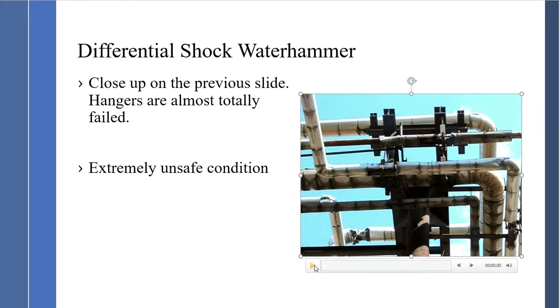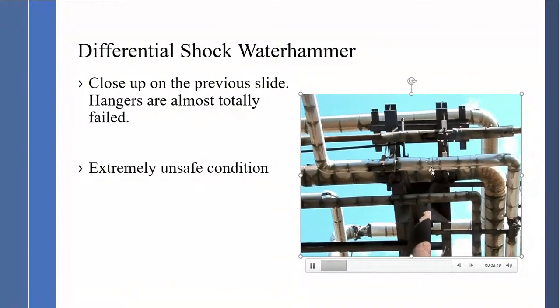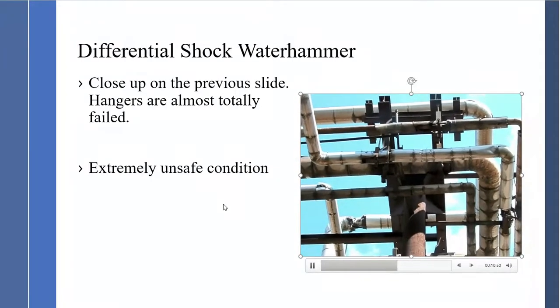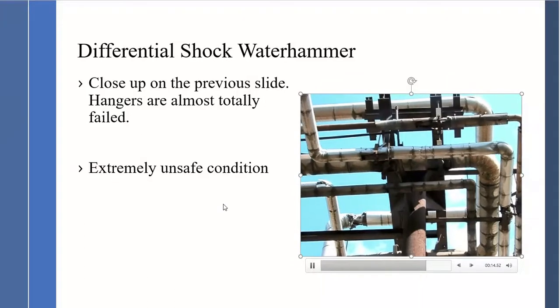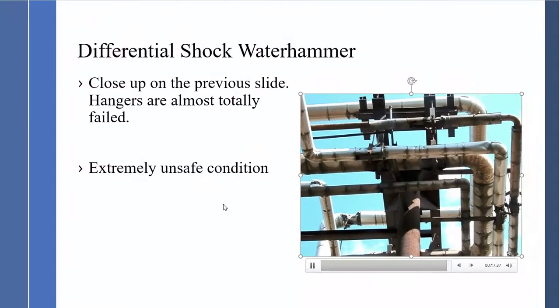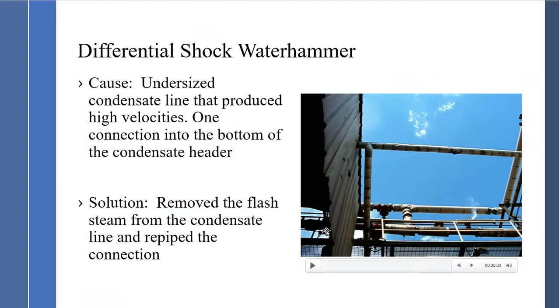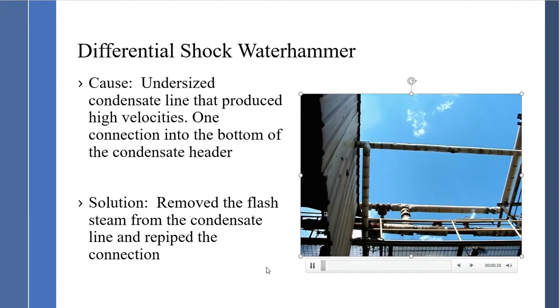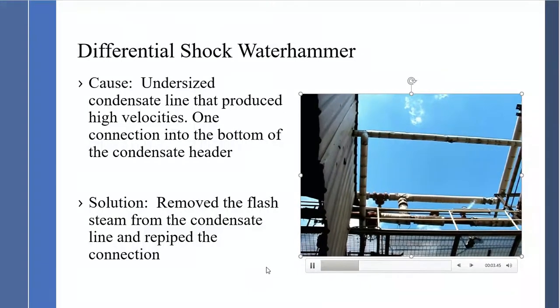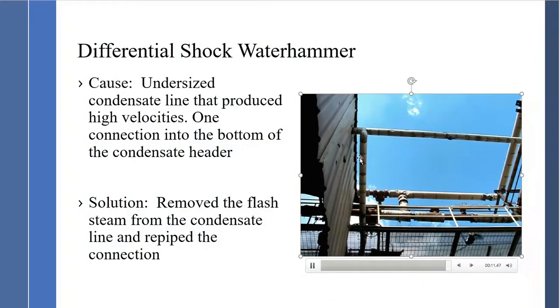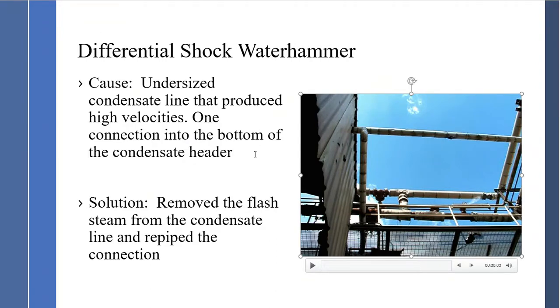A close-up shows visible damage to the pipe support from the water hammer effect. This was an unsafe condition due to plant personnel being in the area. Correction happened immediately. Another condensate line example shows an undersized line producing high velocity, with one connection into the bottom of the condensate header. The correction involved removing the flash steam from the condensate line and re-piping the connection to the top of the header, which eliminated the water hammer.